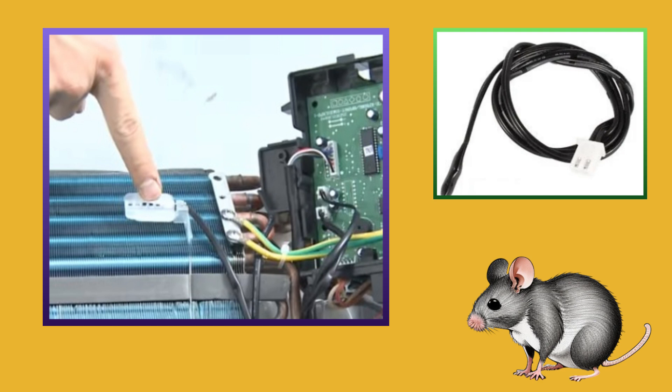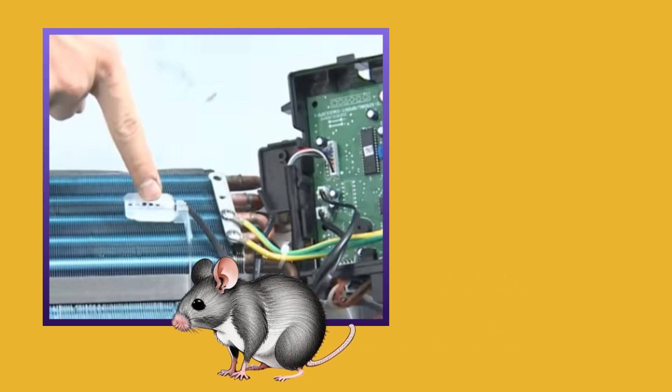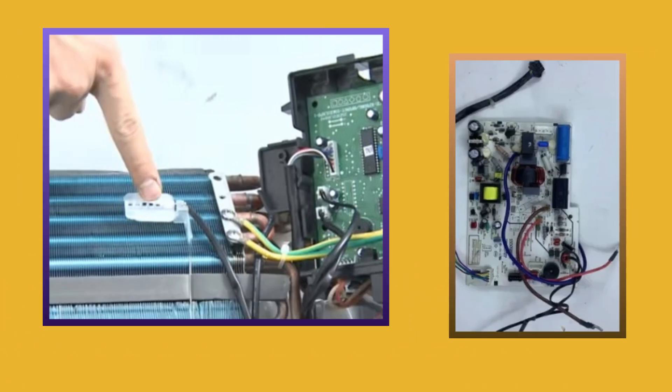And if the rat has not cut the wire of the room temperature sensor and still this error is coming, look at the sensor connector in the PCB. This error also occurs due to loose connection. If you remove the connector and reinsert it, this error will be fixed.